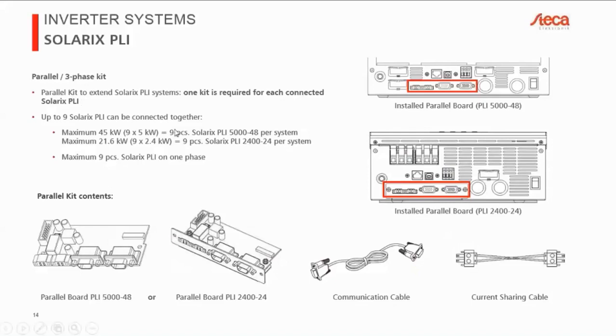So for the 5 kilowatt version, times 9 means the maximum system size is 45 kilowatts. Up to 9 can either be put on a single phase or distributed across 3 phases. Same goes for the smaller 2.4 kilowatt version, which means that our maximum synchronized system size is 21.6 kilowatts.